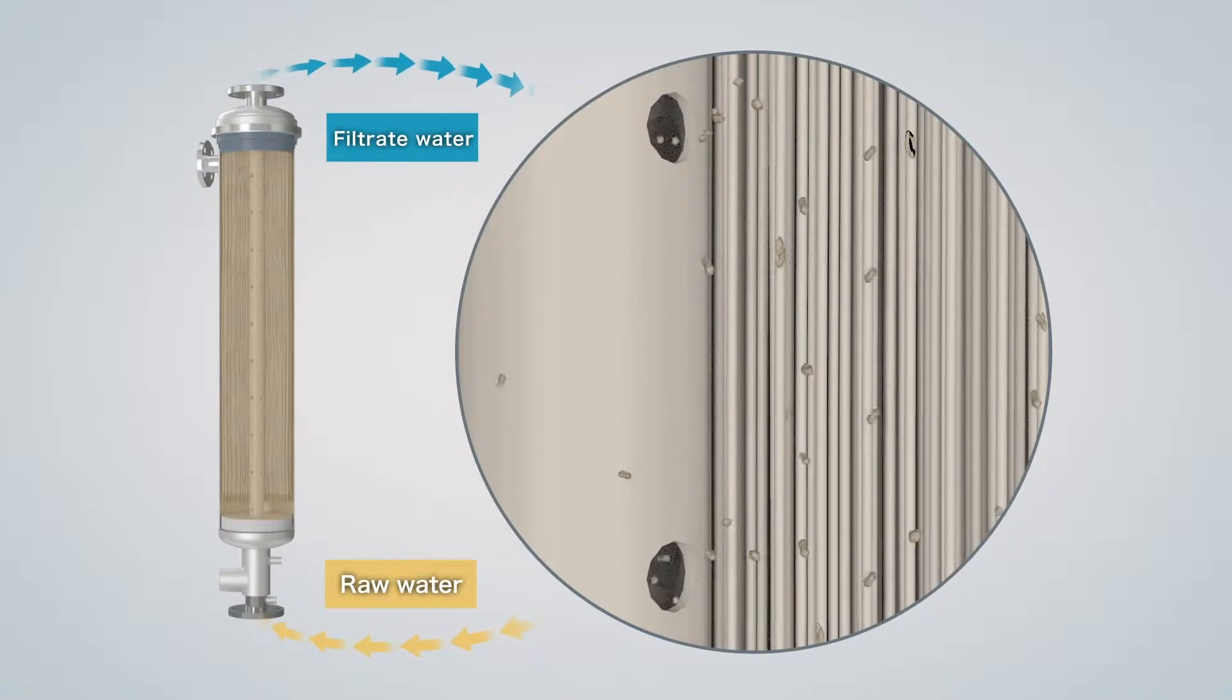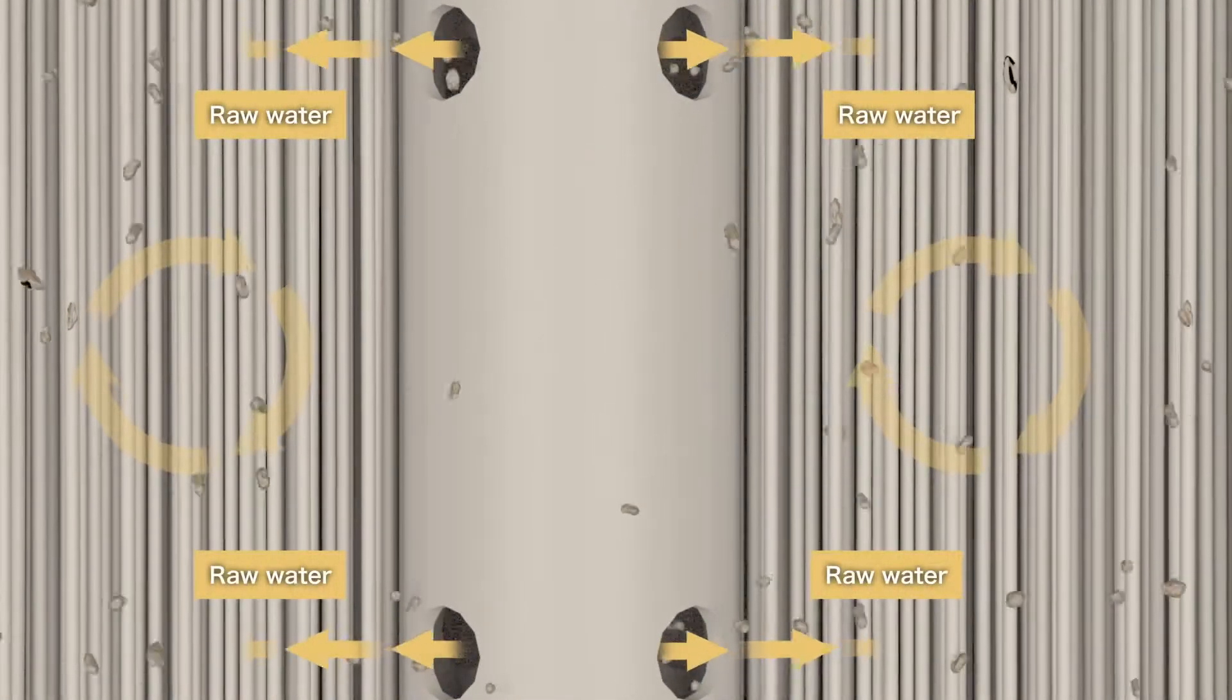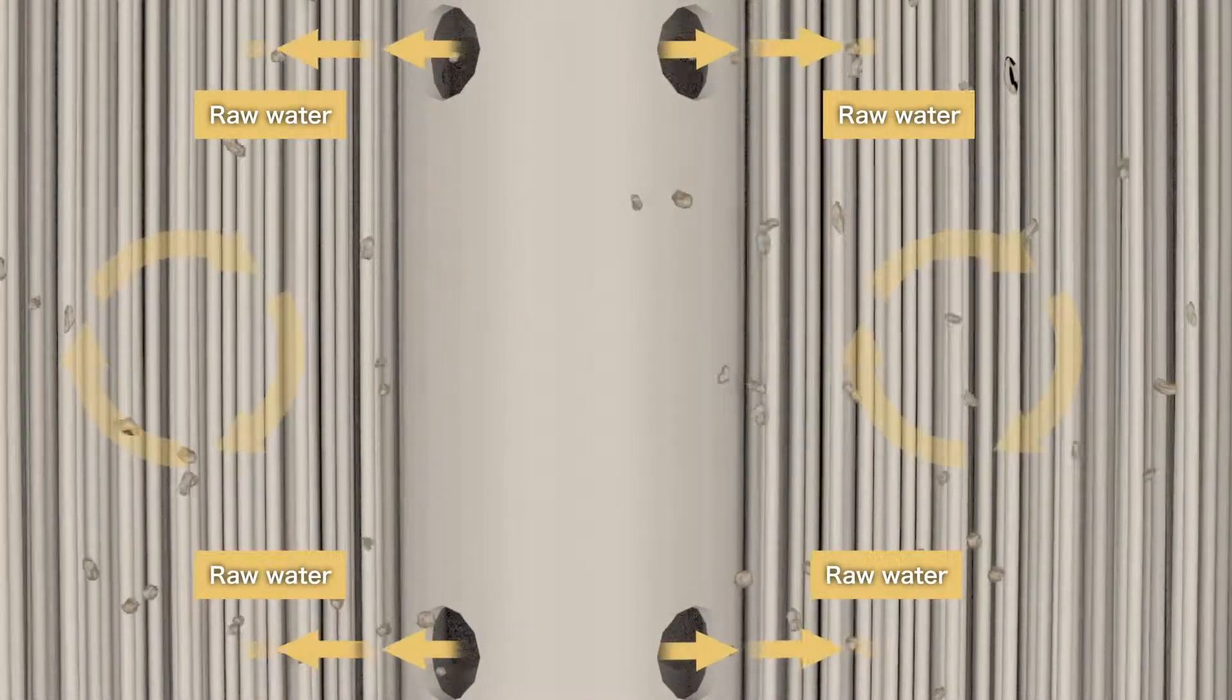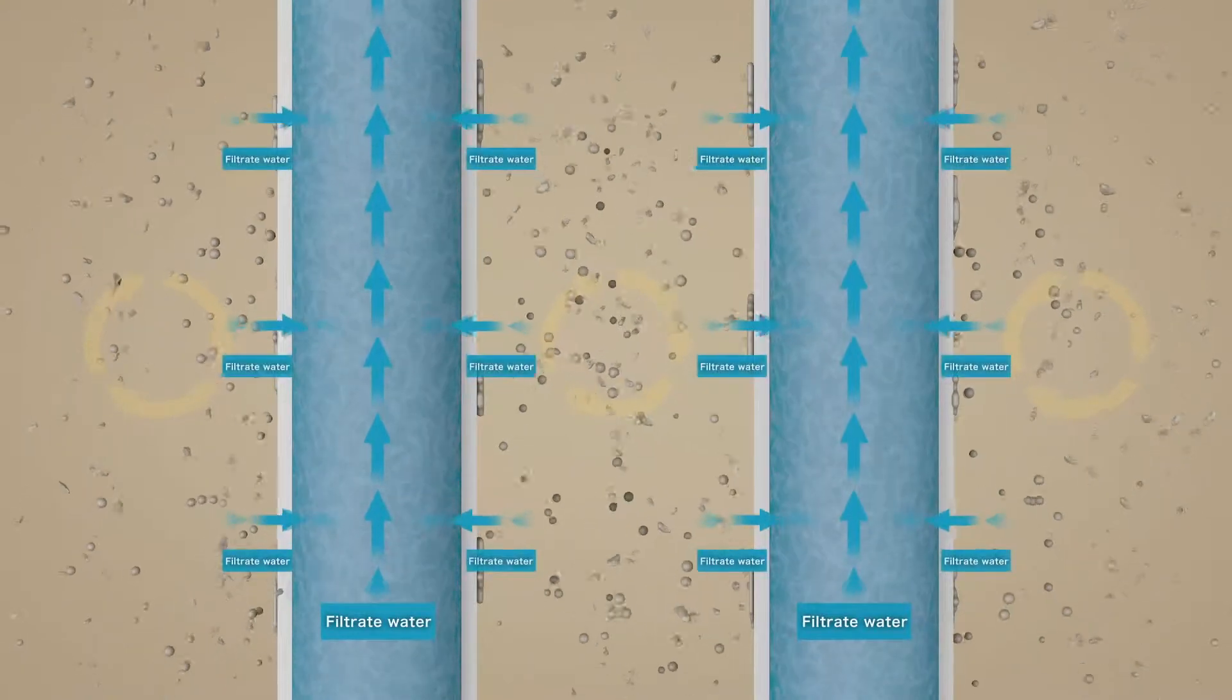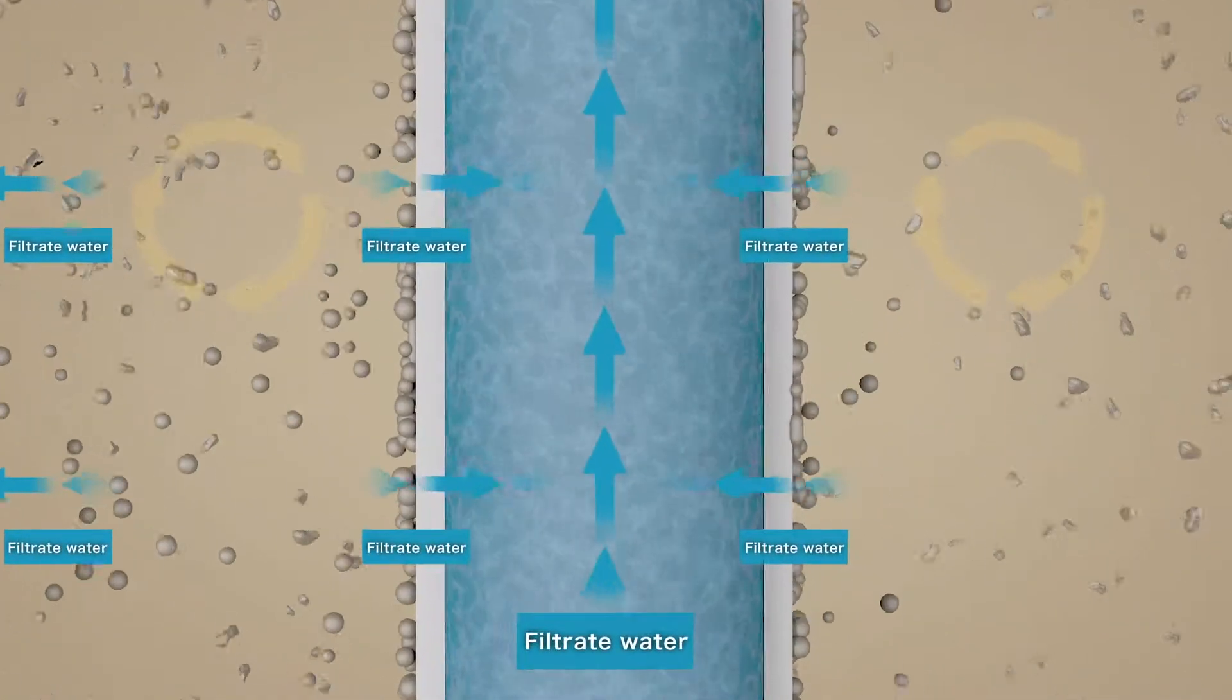By distributing raw water from the center distributor, a flow occurs on the surface of the hollow fiber membrane. This flow removes the particles attached on the membrane surface, like cross-flow filtration, and so inhibits particle accumulation.